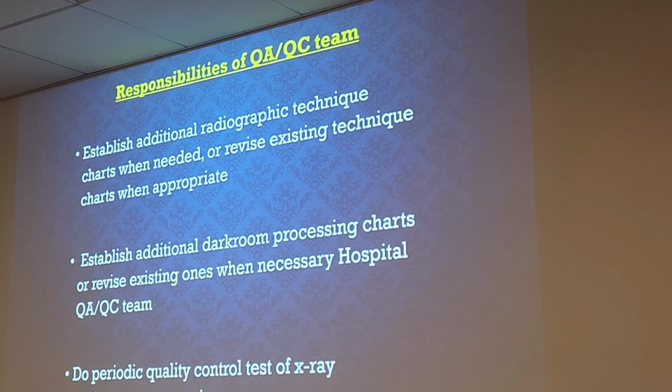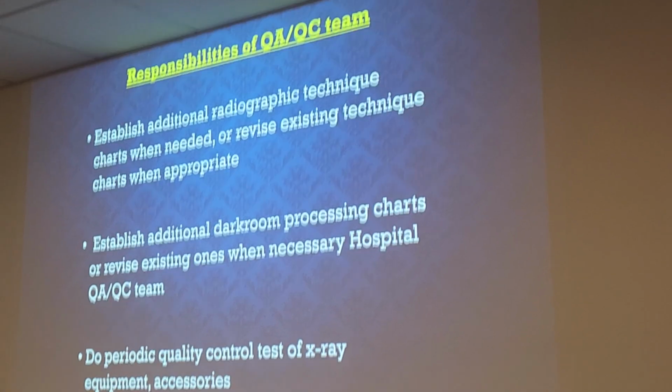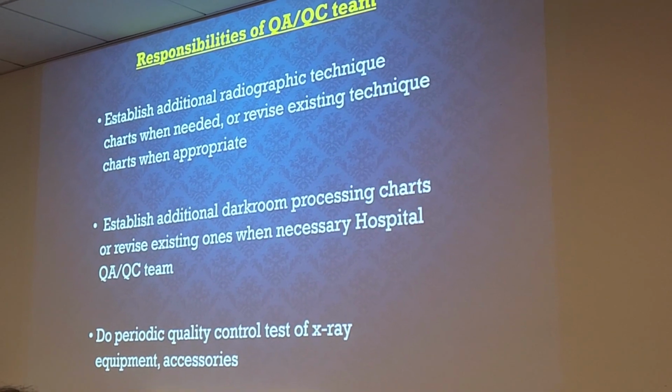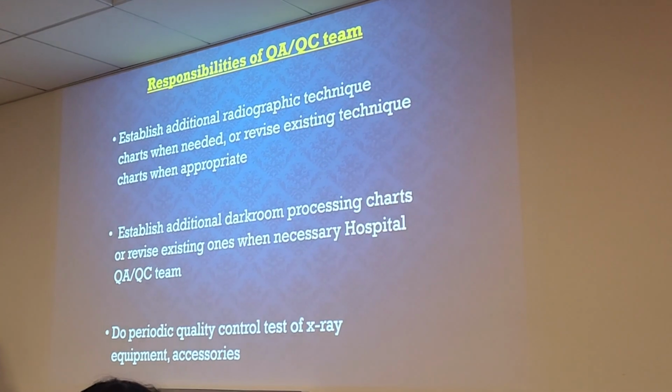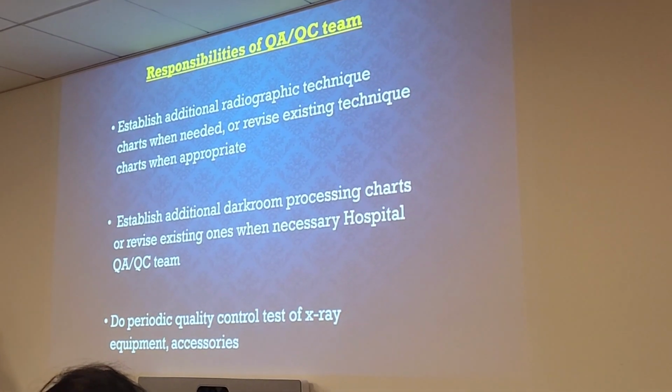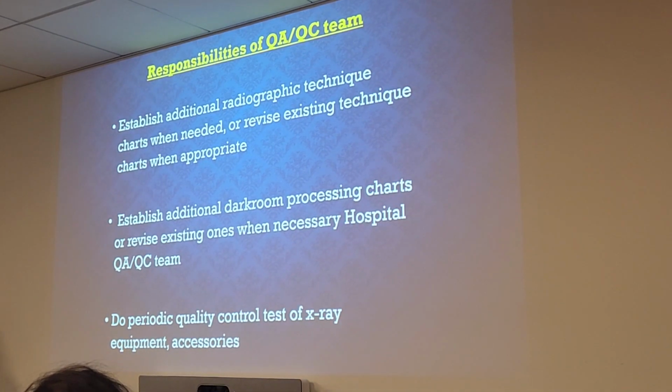Another responsibility of the QA/QC team is the periodic quality control testing of all of your imaging equipment and your accessories. Accessories meaning thyroid shields, lead aprons, things of that nature.